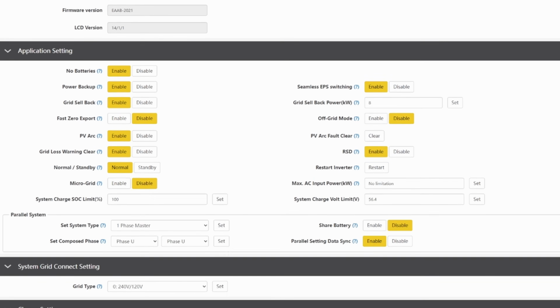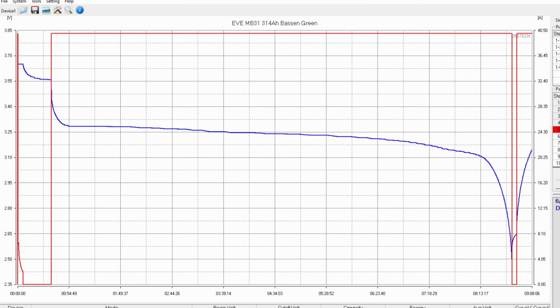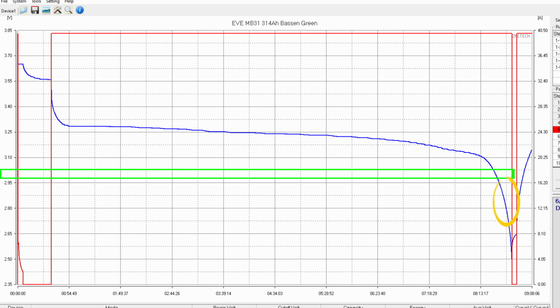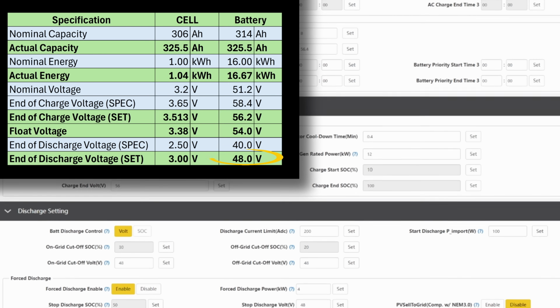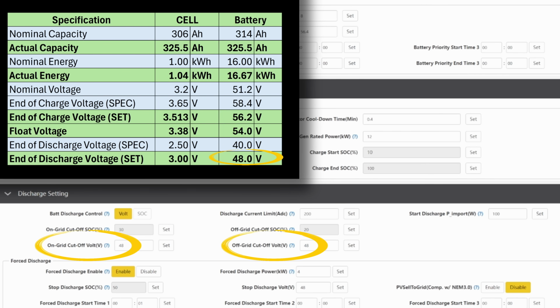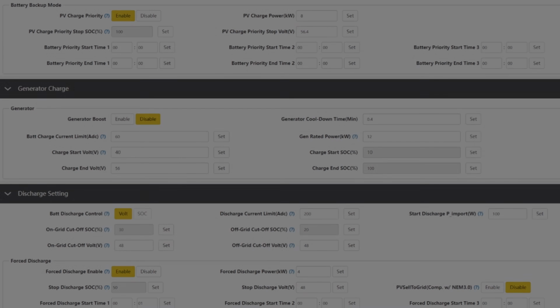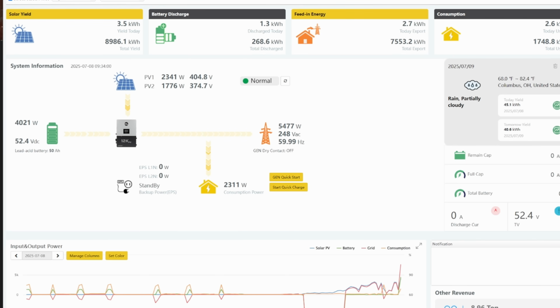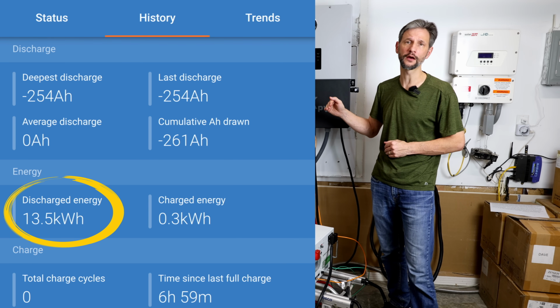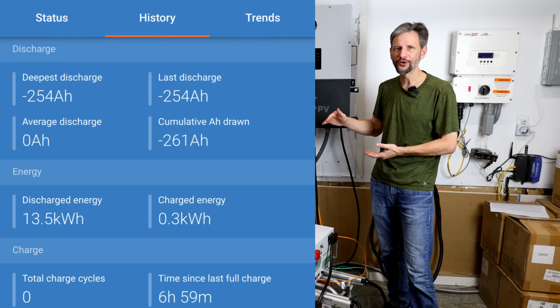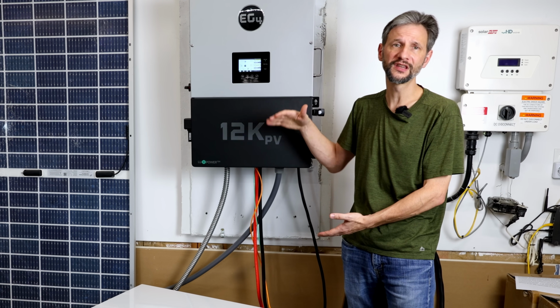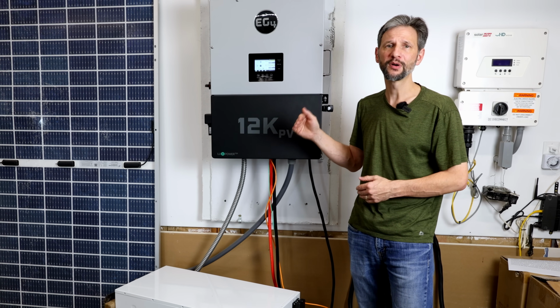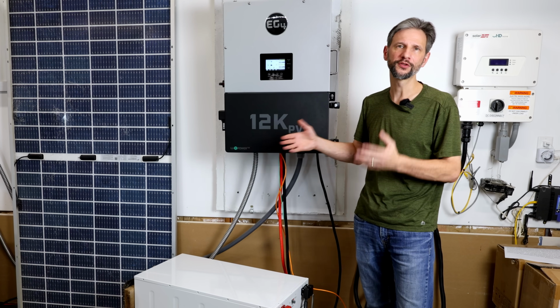The BMS should be set to the minimum of 2.5 volts, but you can see that there's no real capacity left past about 3 volts. So I can set the pack minimum at 48 volts to reduce the stress on the battery and still use the majority of the battery capacity. After charging and discharging the battery with those more narrow voltage settings, I applied a 4,000 watt load and I had a usable capacity of 13.5 kilowatt hours. Of course, if I lowered the load or expanded the voltage ranges, we would get the full 16.8 kilowatt hours. But this shows a practical worst case with those limited settings.